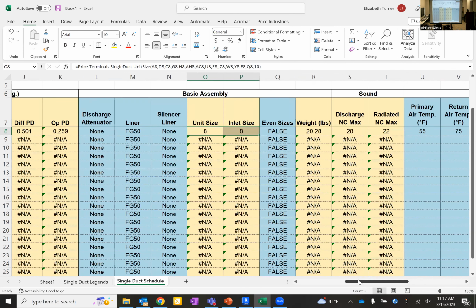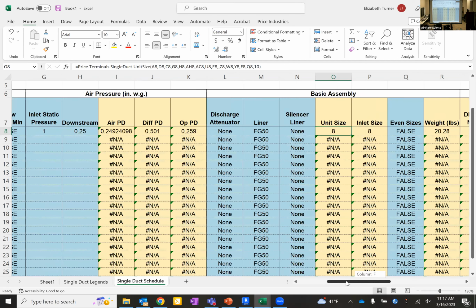I did not specify an 8-inch inlet. It chose an 8-inch based on the airflows that I fed it. If you have company standards, you can absolutely override that. If I change this to, I just literally typed in 10, it would fix all the water coil performance and update it. So it has a function to auto size, but you can remove that.